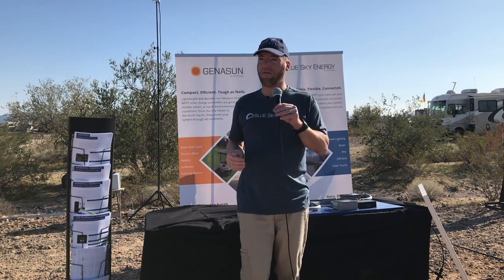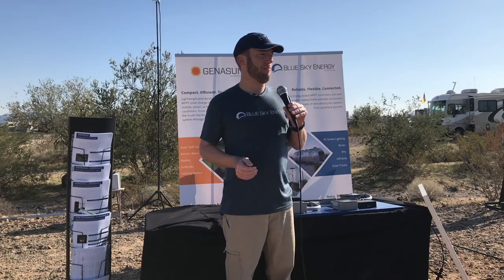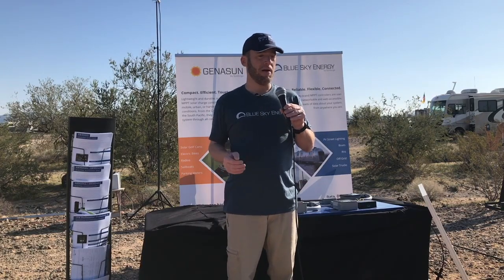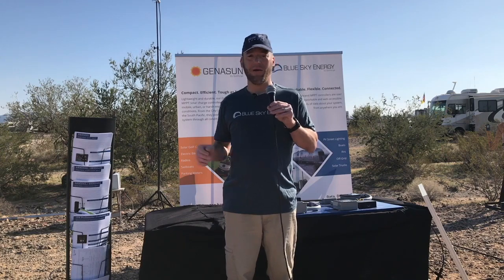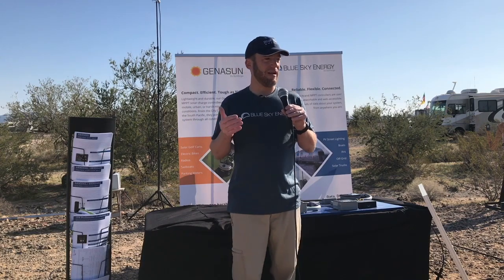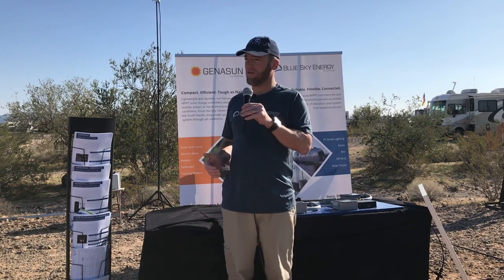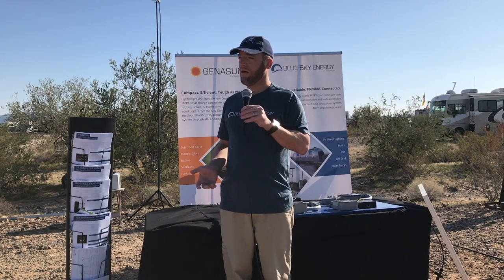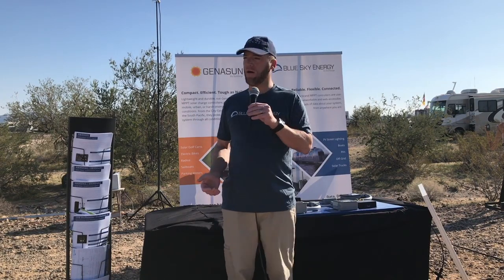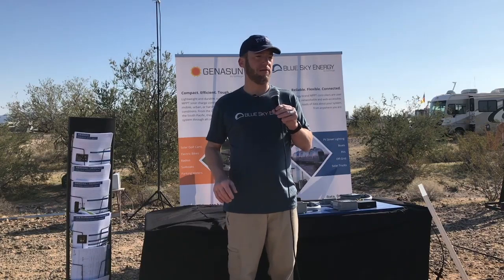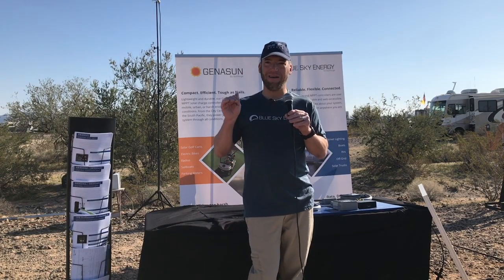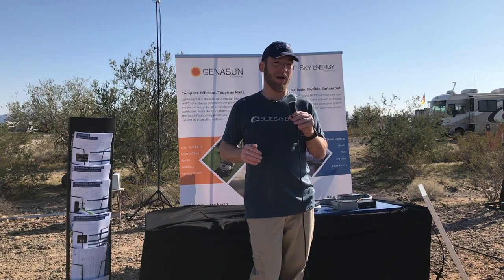Another thing to increase your battery's longevity: I always recommend with lead acid batteries, a battery temperature sensor. They're not very expensive, like 30 bucks, because batteries like to be charged at slightly higher or lower voltages depending on how hot or cold they are. The colder the battery, the higher voltage it wants; the warmer, the reverse, the lower voltage it wants. For a small investment, you can easily increase your battery's longevity by quite a bit.